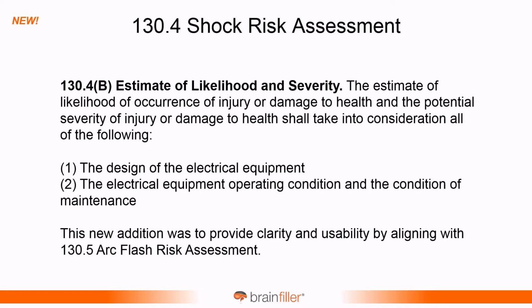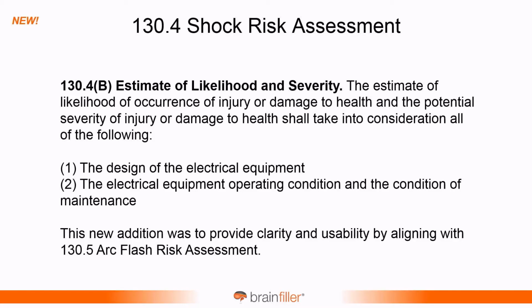The shock risk assessment. So there was language that is part of the arc flash risk assessment that has now been duplicated, and what that language looks like right here. Estimate the likelihood and severity. The estimate of the likelihood of occurrence of injury or damage to health and the potential severity of the injury or damage to health shall take into consideration all of the following. Number 1, the design of the electrical equipment. Number 2, the electrical equipment operating conditions and the condition of maintenance. And so this is really to align it with what we already had in 130.5, because the same type of language exists for the arc flash risk assessment.